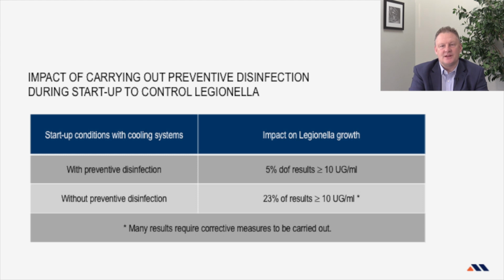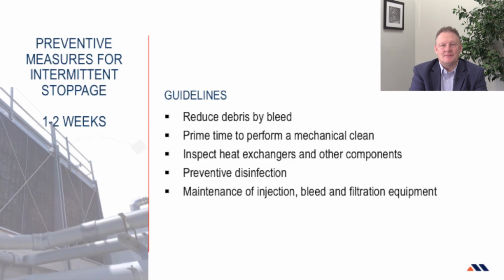This table demonstrates the ratio of Legionella counts in terms of cooling towers that were proactively and preventatively disinfected versus towers that were not disinfected. You see that in the towers not disinfected, there's a significant increase in the Legionella concentration as measured by qPCR. When a system is temporarily stopped for 1 to 2 weeks or longer, there are guidelines to follow.